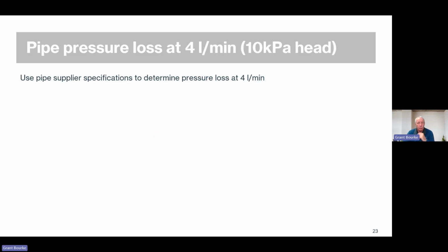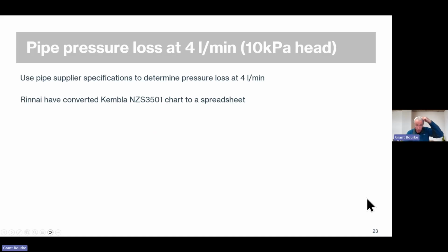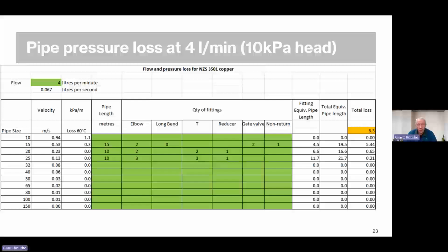So we're going to use the pipe supply specifications to determine what that pressure loss is at 4 litres a minute. Now, I'm sticking with 3501 in this presentation. So what we've done is we've taken the 3501 specification sheet and we've converted it into a spreadsheet. And if you use this pipe material, at the end, we'll give you a link to the spreadsheet that you can download and use for yourself. So what we've done at the top left here, we've put our flow rate in, we've put the length of pipe in that we're going to use, and then we've put in the number of fittings that we're going to put in each length of pipe, which will increase the effective length of pipe. So we've put all that in, and it's popped out that we've got just over a 6 kPa pressure loss around that ring main.